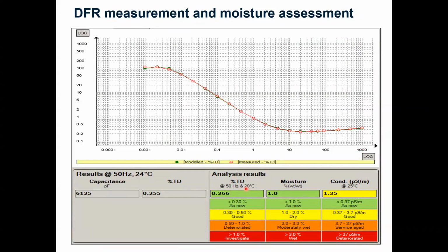So we do the measurement, we analyze the curve, and we get the moisture content here in terms of weight in percent. And we have also tangent delta at 20 degrees and oil conductivity at 25 degrees, so according to standards. And then we have also the Megger guidelines here, showing that if you have a green moisture, then it means it's as new. And if it would be yellow, then it would be still dry. And then orange would be moderately wet and red would be wet.